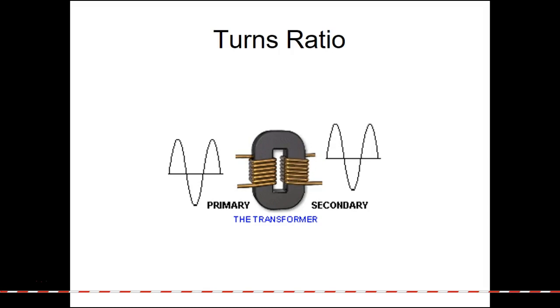So we can buy these things that'll either step the voltage up or step it down. We do that over in the robotics lab. We have two robots over there that run off 440, and there isn't 440 in that building. So for both of those, we have to have step-up transformers to step the voltage up to run those robots. If we tried to run them on 208, they wouldn't work at all—they'd be at a quarter of the power, and everything wouldn't be right.